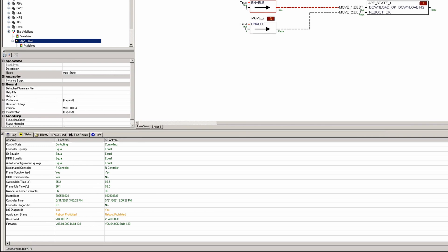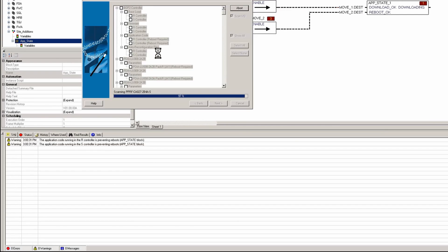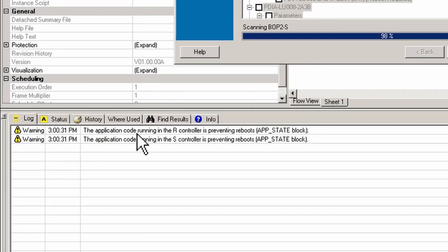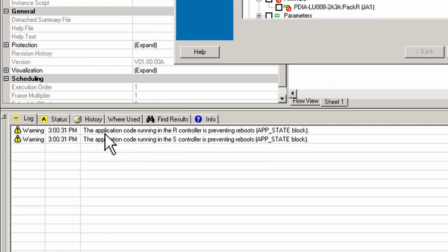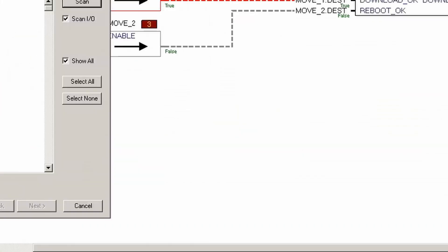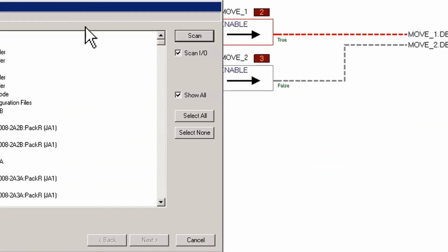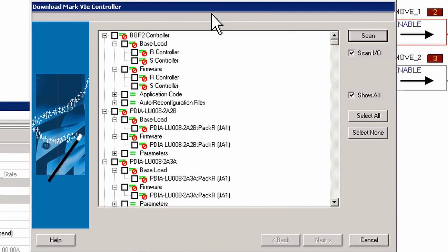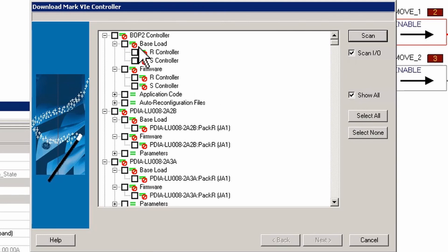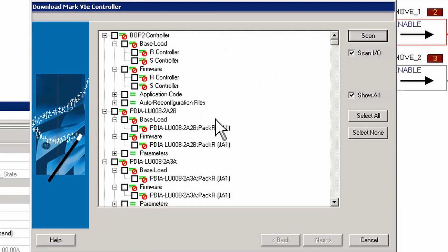You'll see that this next time I'm going to go make a download and you'll notice I get a message here right off the bat that says the application code running in the R and S controller is preventing reboots. That's this block. And you'll also see there's some new things in the download window that we hadn't seen before.